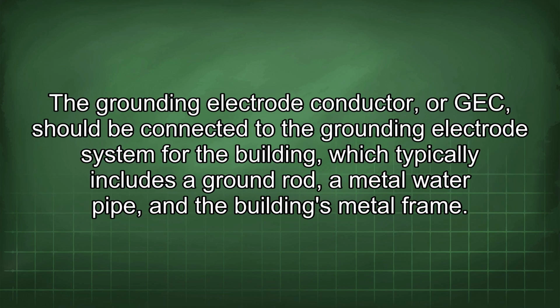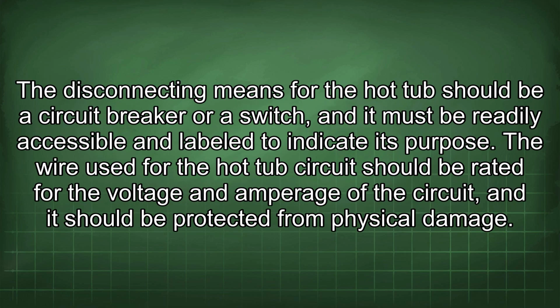The grounding electrode conductor, or GEC, should be connected to the grounding electrode system for the building, which typically includes a ground rod, a metal water pipe, and the building's metal frame. The disconnecting means for the hot tub should be a circuit breaker or a switch, and it must be readily accessible and labeled to indicate its purpose.